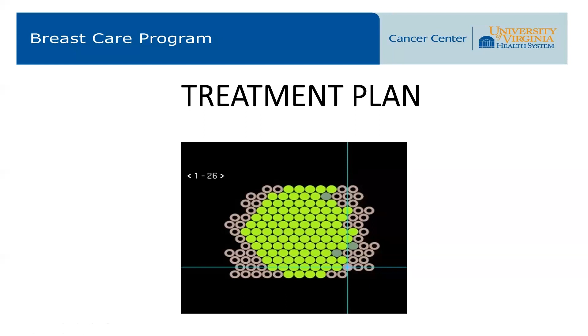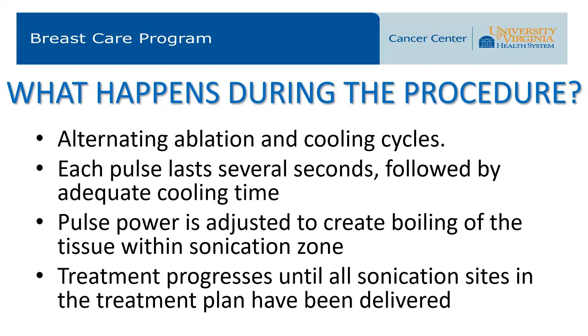During the procedure, there are alternating ablation and cooling cycles. Each sonication pulse lasts several seconds, followed by an adequate cooling time, which typically varies between 10 and 25 seconds. The pulse power is first adjusted to create boiling within the tissue in the sonication zone, and then once we determine the adequate pulse power, the treatment progresses until all the sonication sites in the treatment plan have been delivered.